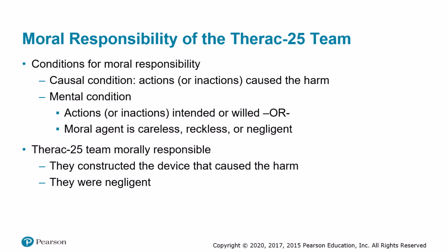So the design team took a number of actions that fall into these three categories. It constructed a system without hardware interlocks to prevent overdoses, or to keep the beam from being activated when the turntable was not in a correct position. The machine had no software or hardware devices to detect an accidental overdose. Management allowed software to be developed without adequate documentation, and it presumed the correctness of reused code and failed to test it thoroughly.